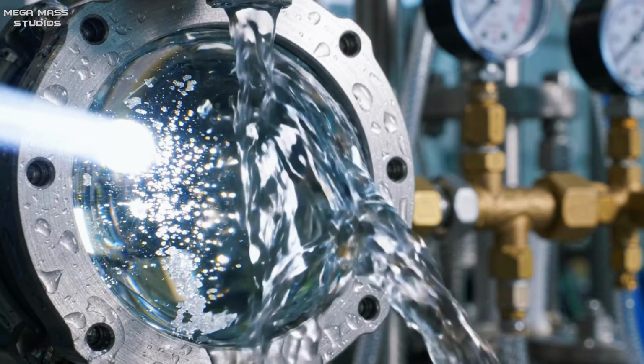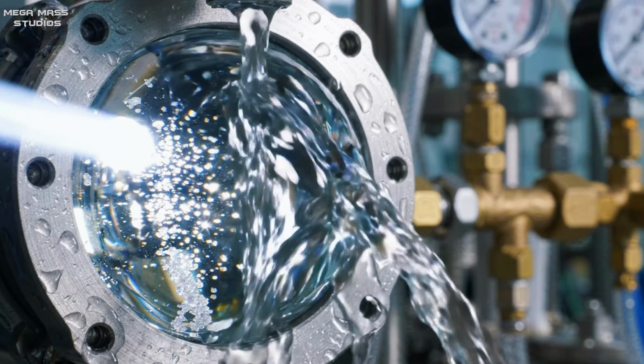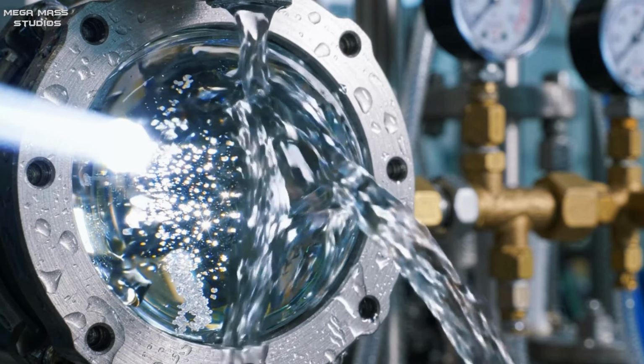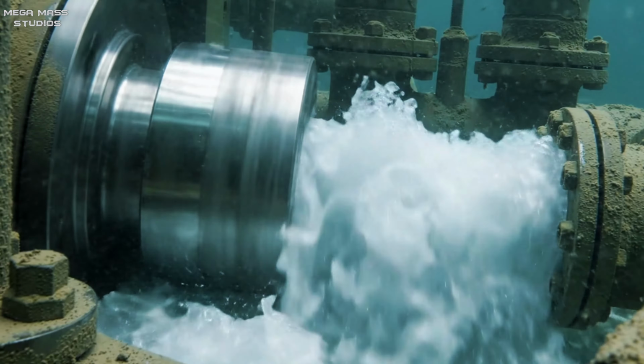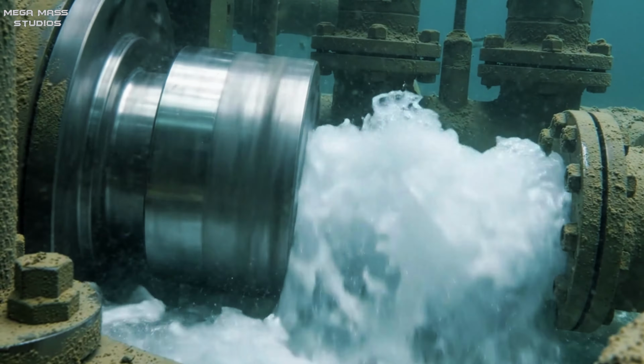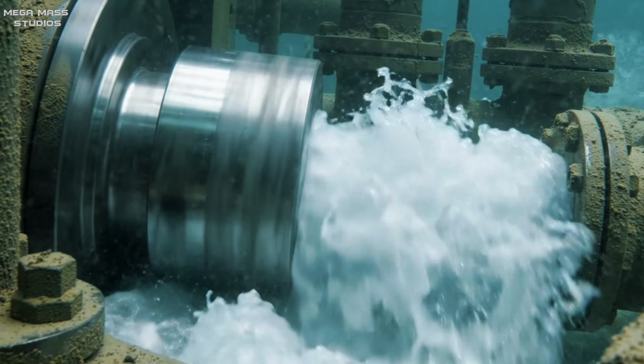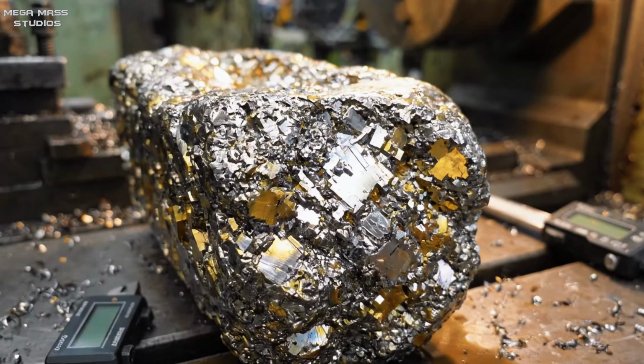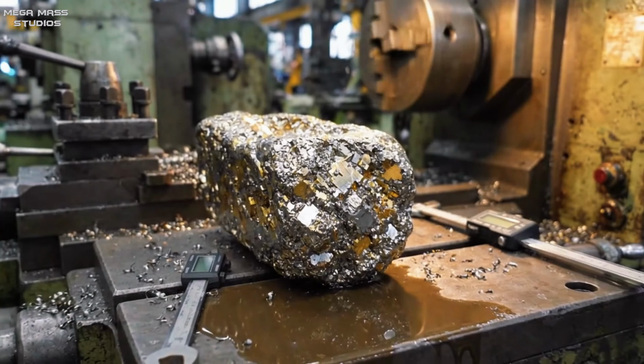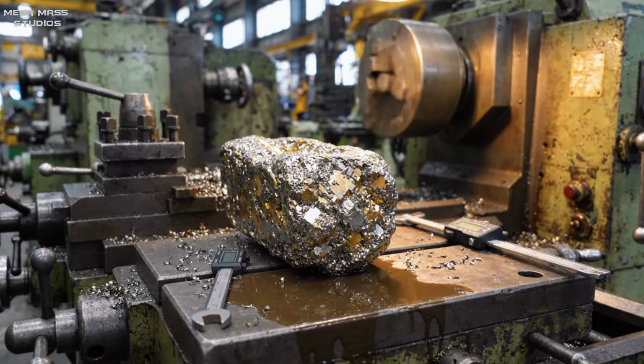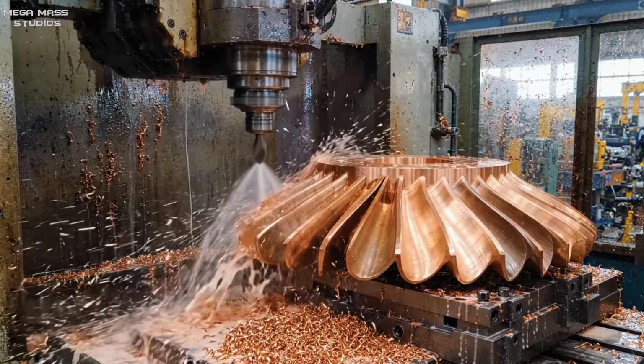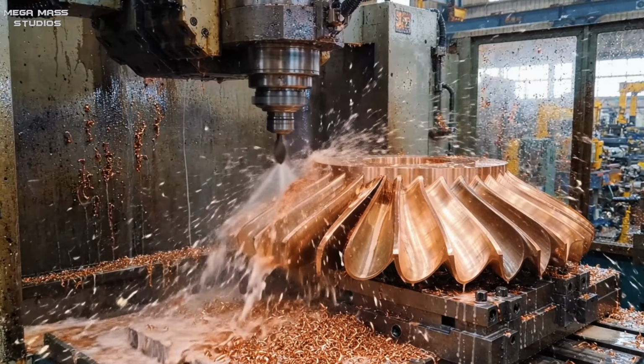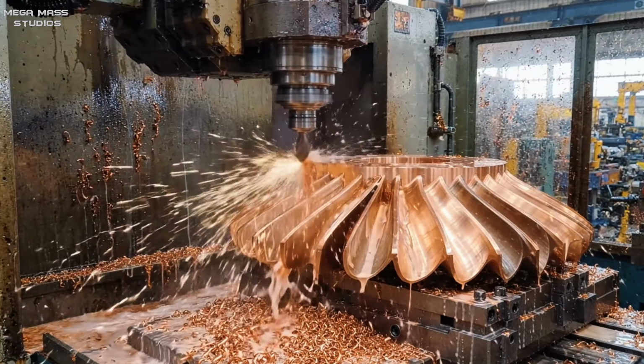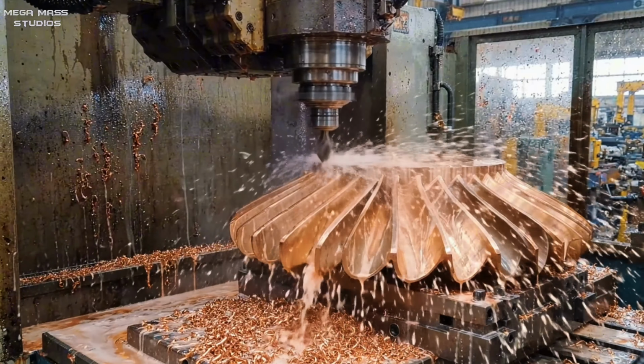Despite passive settling, microscopic quartz particles still remain suspended in the fast-flowing water column. These ultrafine particles act like liquid sandpaper, threatening the structural integrity of the main turbine impellers. This is why the metallurgical composition of the impellers must exceed standard industrial hardness ratings. Each impeller blade is forged from a high-density nickel-aluminum-bronze alloy, designed to resist extreme micro-impacts.